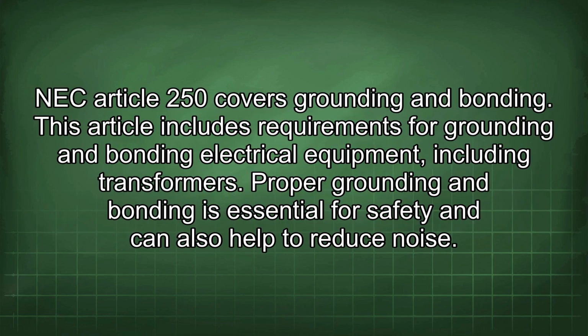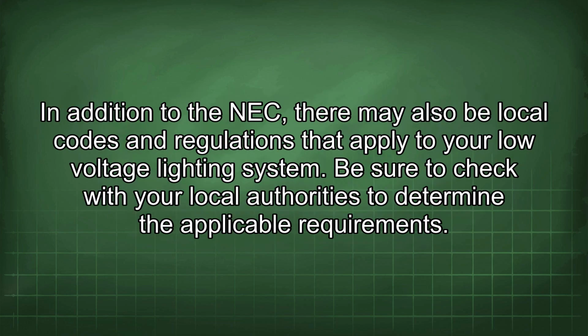NEC Article 250 covers grounding and bonding. This article includes requirements for grounding and bonding electrical equipment, including transformers. Proper grounding and bonding is essential for safety and can also help to reduce noise. In addition to the NEC, there may also be local codes and regulations that apply to your low-voltage lighting system. Be sure to check with your local authorities to determine the applicable requirements.